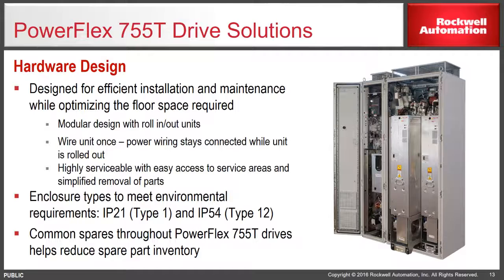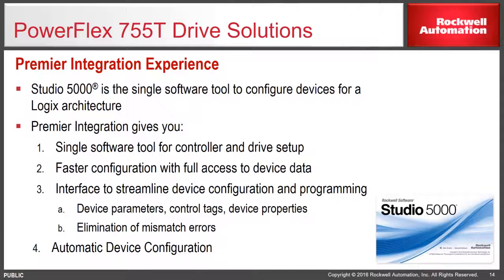Premier Integration. Studio 5000 is a single software tool to configure devices for a Logix architecture. Premier Integration gives you a single software tool for controller and drive setup, faster configuration with full access to device data, an interface to streamline device configuration and programming, device parameters, control tags, device properties, and elimination of mismatch errors. Automatic device configuration is another feature enjoyed in the Logix environment.